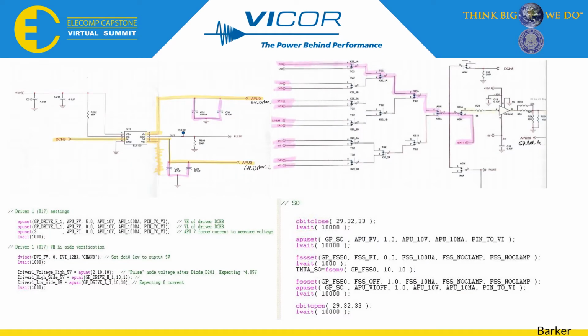Here we can see some of the components tested on the P014 probe card and the corresponding code created to carry out the tests. The schematic page on the left shows one of the P014 drivers in which voltage is forced and measured across the low and high pathways. On the right is the test of a pathway through various switches, switching those required to complete the path, then forcing and measuring voltage at the endpoint matrix pin to ensure the components along the path are correct.